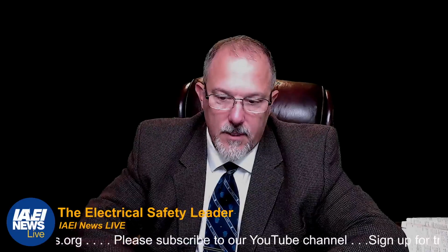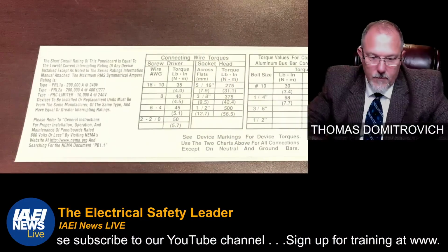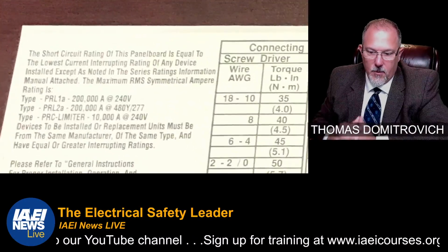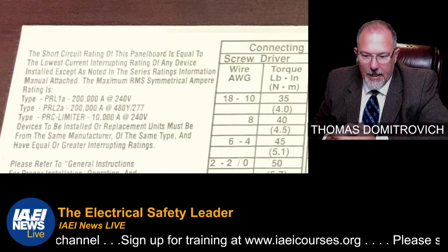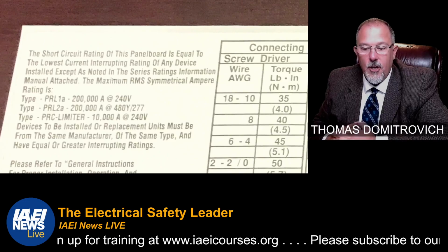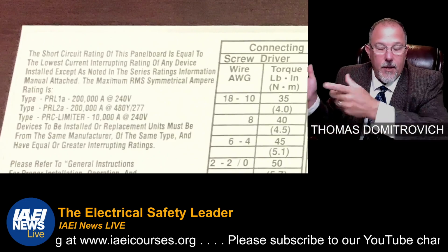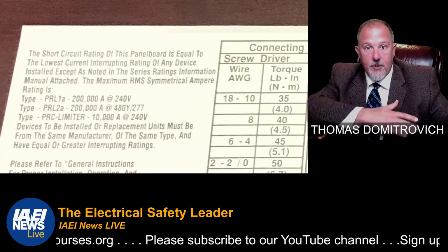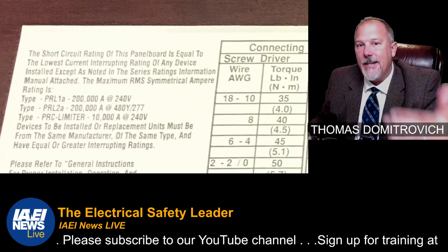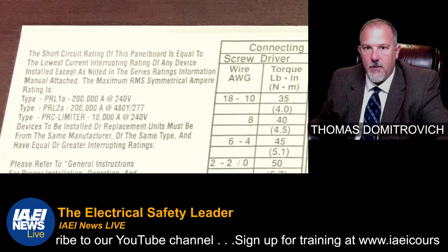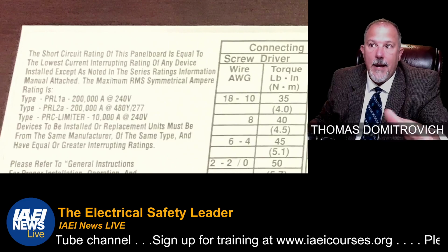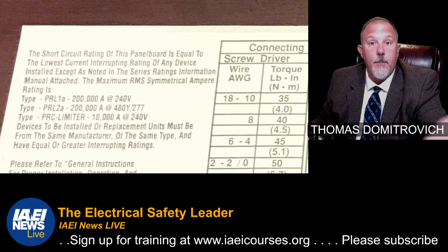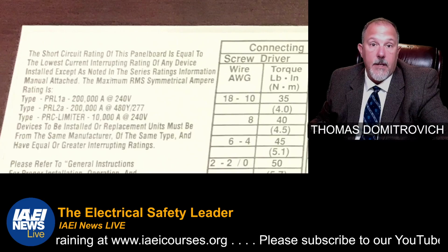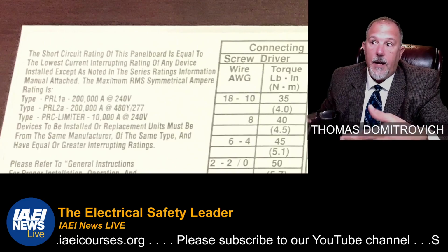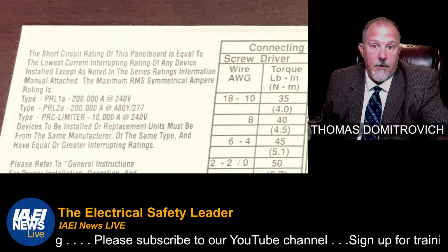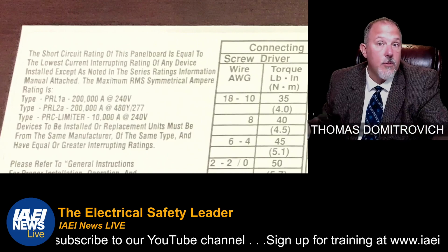Here we go. Here's another one. Here's a label here. The short circuit current rating of this panel board is equal to the lowest current interrupting rating of any device installed, except as noted in the series rating information manual attached. And that other label that I was showing you, that was a series rating table, told you what had to be upstream and what had to be downstream. So I can't mark in the factory a short circuit current rating outside of maybe a fusible panel, right? A fusible panel with a fuse as a main, I can mark that because I have rejection features, etc., that will keep it at 100,000 amps or 200,000 amps.